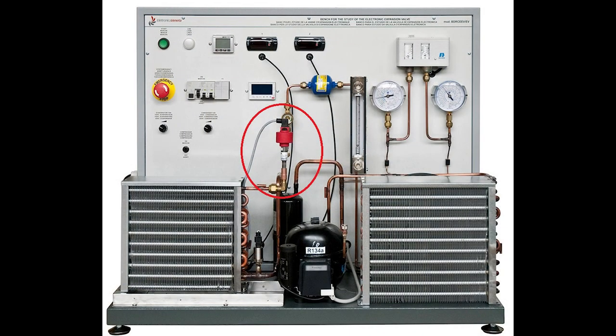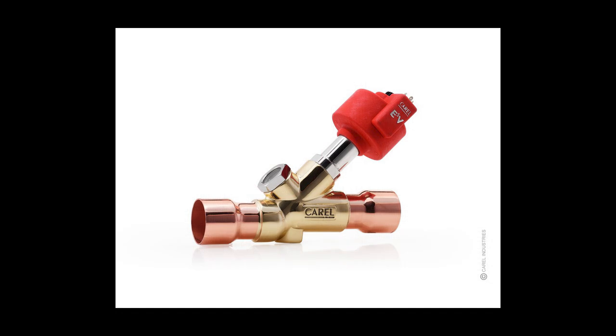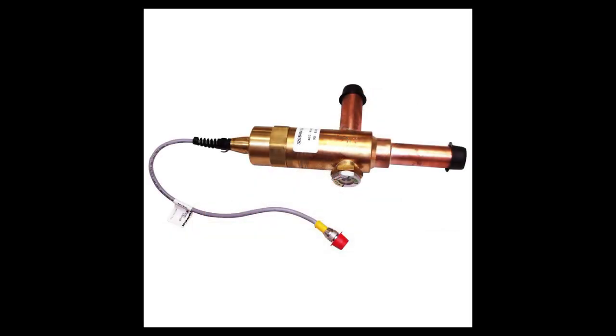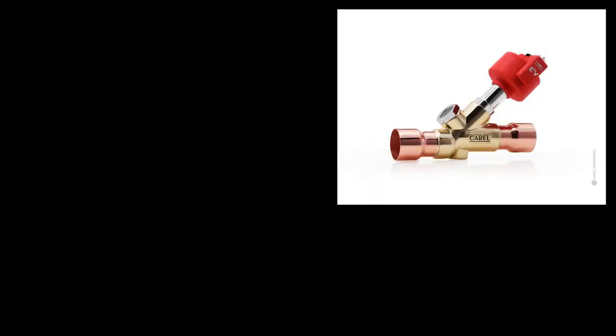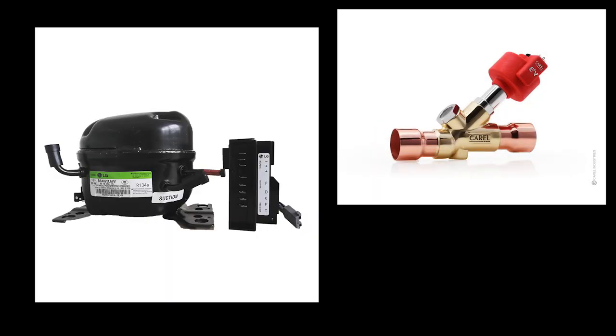A newer technology is called the EXV or electronic expansion valve which solved most of the TXV's shortfalls. The EXV uses a tiny little motor to deliver a precise amount of refrigerant according to the demands of the system. The EXVs are becoming widely available in all types of refrigeration systems because they're the most efficient means of metering the refrigerant. Combining an EXV with an inverter drive compressor is going to create one of the most efficient refrigerator systems available, albeit at a cost.